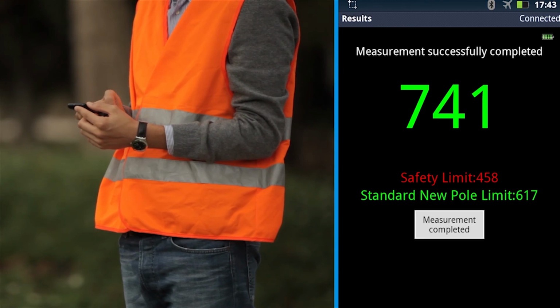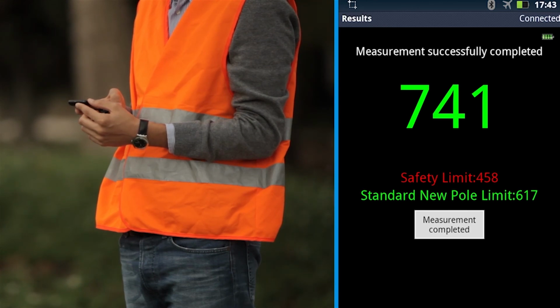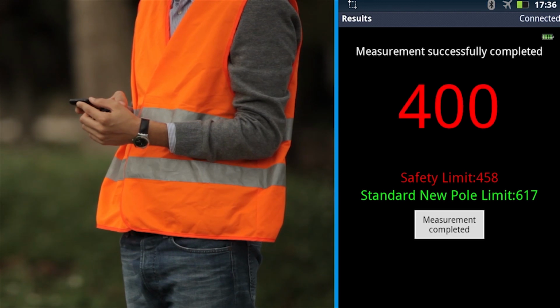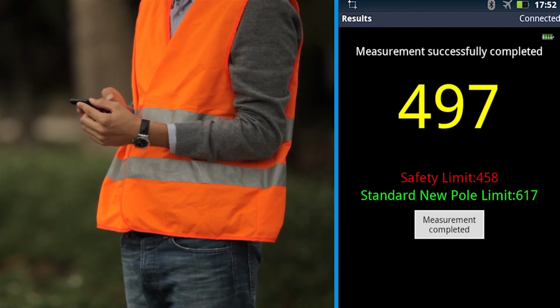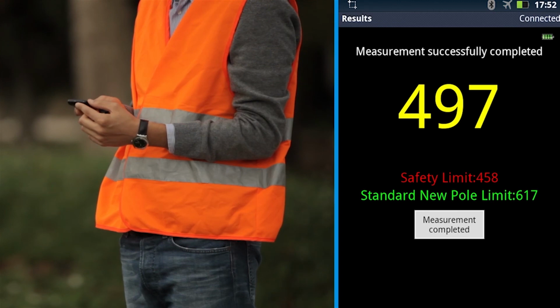In case the UBS is above the green threshold, the result is shown in green to indicate that the pole is good. In case the UBS is below the red threshold, the result is shown in red to indicate that the pole is not good and has to be replaced. In case the UBS is in between the two thresholds, the result is shown in yellow to indicate that the pole requires attention.